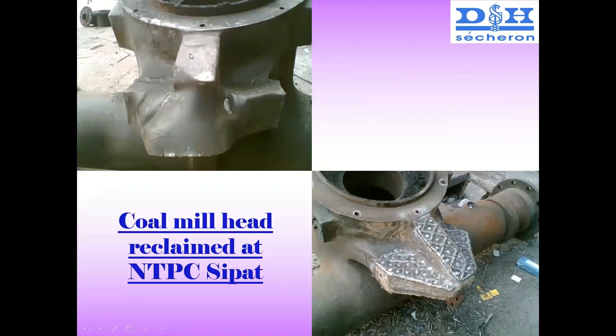If you see this spider, notice the way it has gotten worn out. Its original shape was like this, but it has worn out to this stage. We have done the entire reclamation there. We have not done the entire build-up because it requires a lot of electrodes. Initially, we inserted mild steel plates and blocks to maximize build-up, and then hard facing was done over the final build-up.